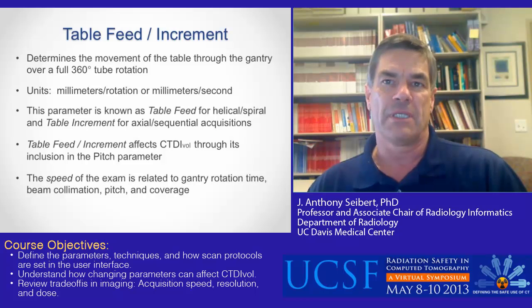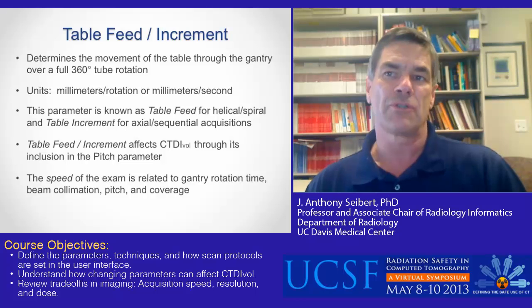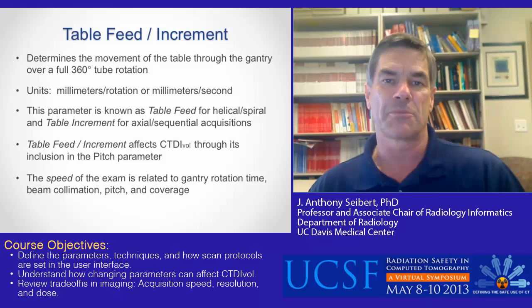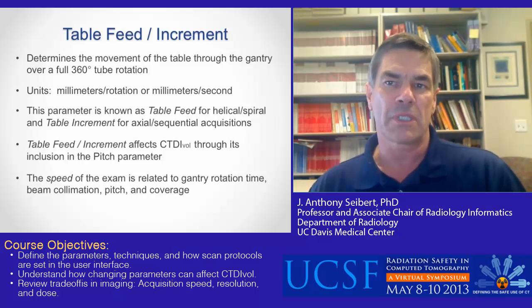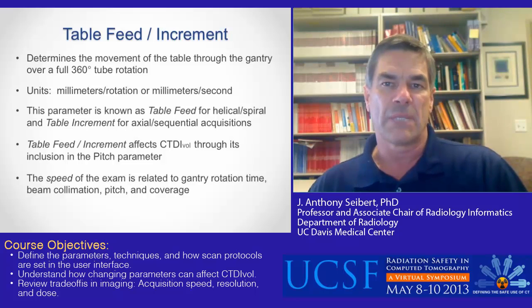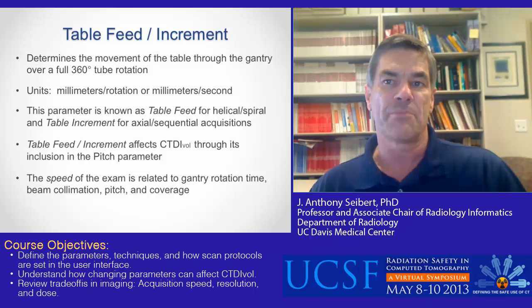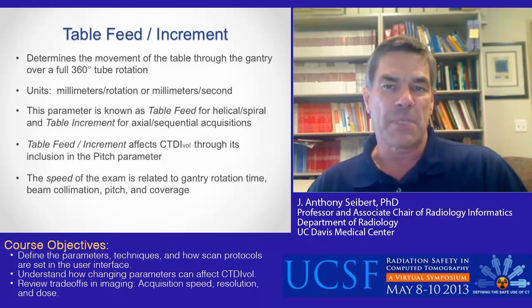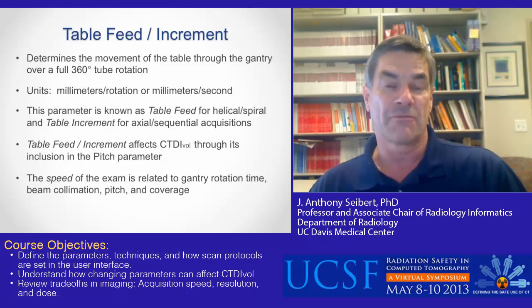Table feed is the movement of the table that occurs during a 360-degree tube rotation, in units of millimeters per second. Table increment is the movement of the table between scans for axial or sequential acquisition. Table feed and increment affect CTDI vol through the pitch parameter, as will soon be explained. The speed of the exam is related to gantry rotation time, beam collimation, pitch, and coverage.